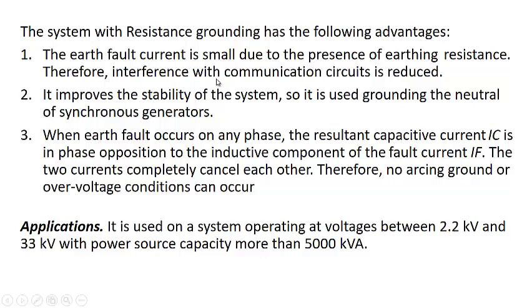And in case of a solidly grounded system, it has a disadvantage that the ground current, or we can say the neutral current, is very high, and it results in interference with the communication circuits. But in case of resistance grounding, because the current is less, there will be less communication circuit interference. Also, it improves the stability of the system, so it is used in grounding the neutral of a synchronous generator. So usually this resistance is used in grounding the neutral of the synchronous generator. So this is actually there.